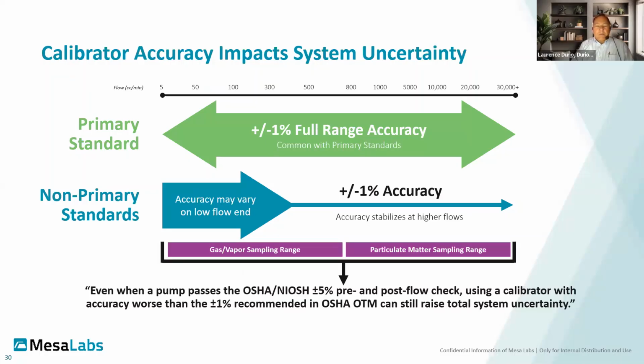Primary standards, particularly piston provers, tend to be very linear, plus or minus whatever that 1%, or in some cases even less than that, across their full range. Some calibrators, if they give a range and you start to see that fixed amount of leakage or loss of accuracy in terms of volumetric cc's per minute, that can exceed that 1% accuracy. The reason that we look at 1% accuracy on calibrators is because we're looking at a 5% total, and we've got about 3% that OSHA says, but I think it was actually a NIOSH study, says is attributable to pumps. So they really want the calibrator accuracy not to be the limiting factor. They want the pumps, which tend to be somewhat less stable than calibrators, to be your limiting factor.